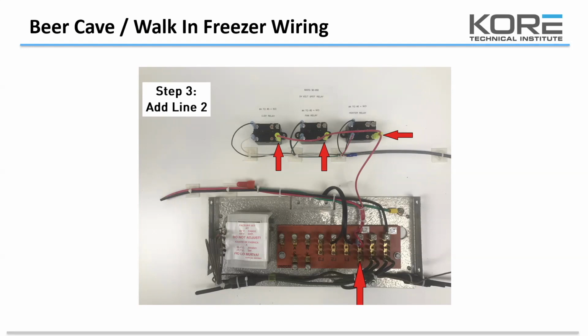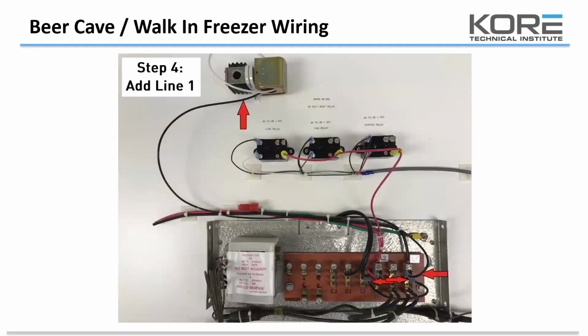The L1 is going to be the one side of your fixture control, and L2 will be the other side to complete the circuit. You'll see that the red wire that we've taken off of L2 is daisy chained to number 4 on each of the relays. The arrows that you're seeing on this particular photo are showing that we are taking the L1 or one side of the leg directly to the solenoid valve. We're also taking it to one side of the fan, and of course the heaters are already attached to H1.